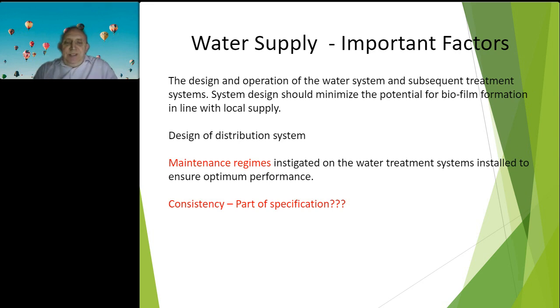The important factors of a water supply. System design, okay? It should always minimize the potential for biofilm in line with local supply, okay? Do we think the material of the pipework is important? If you think in healthcare today, cost is becoming a major factor. We have plastic compositions. Should we be having plastic compositions, or should we stay with traditional copper or stainless steel on our distribution systems? Again, I'll leave that with you.